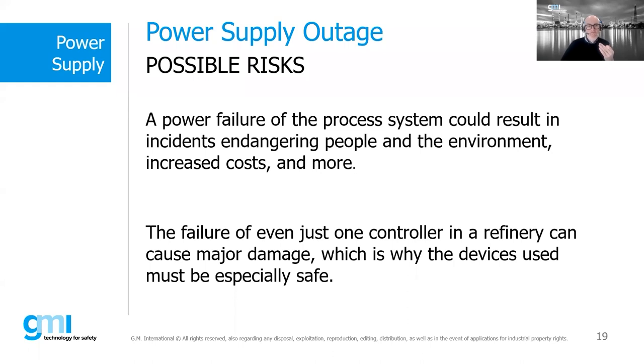Let's analyze what happens when the output voltage of our system reaches an undefined voltage between 2 and 20 volt DC. This condition must be considered a dangerous failure of our power supply, because an incorrectly powered load works, or can work, out of specification. And this leads to a reduction in load performance that can cause a premature instrument failure.